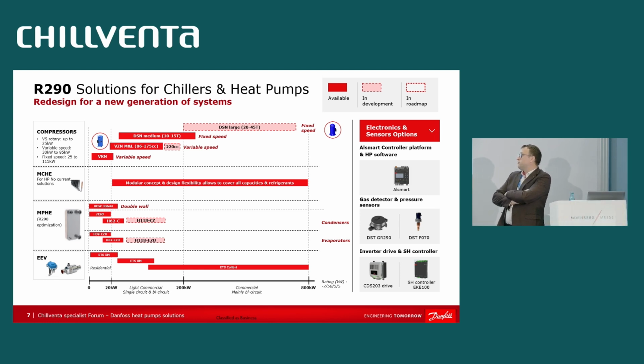In the meantime, we've been working on solutions related to our microchannel heat exchanger. We completely revamped our range of plate heat exchangers to optimize them with propane, meaning we had to redesign the plate and minimize the internal volume as much as possible, allowing OEMs to design units up to 150-200 kilowatt with 5 kilogram of refrigerant.